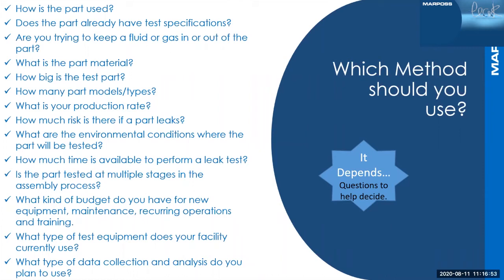How many part models and types? Normally with pressure decay, whether it's differential or absolute pressure decay, you need to have a master part, a reference part that you set up to. If you have a lot of various part models, you would have to have a master part for each one of those. One of the things we can do with mass flow is set the programs up to accommodate slight variations in part volume and things like that. It just affects the cycle time.